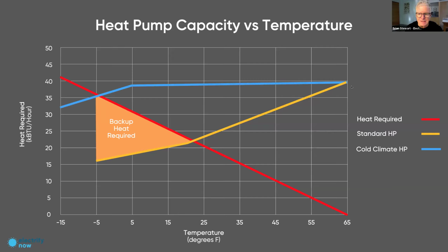You see there's only a very slight decline down to 5 degrees, and there's a lot of the country that's never going to get close to 5 degrees in winter. You do start to lose a little heating capacity below that, but you're still providing a lot of heat even at minus 15. This is just a generic example, and the exact system might look a little different, but in this scenario, with this house's requirements, you only need backup heat at minus 5 degrees.